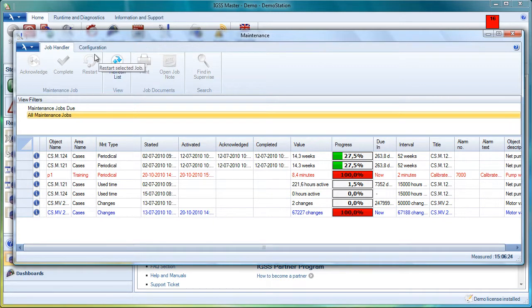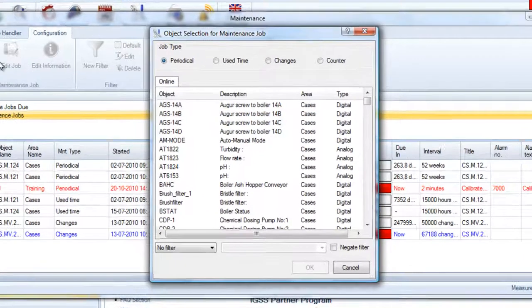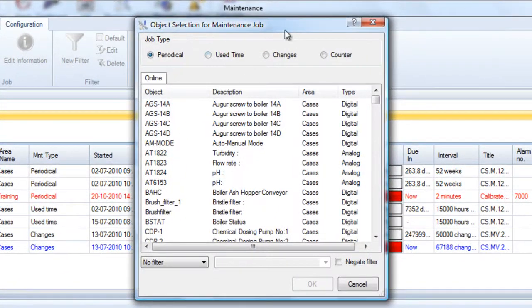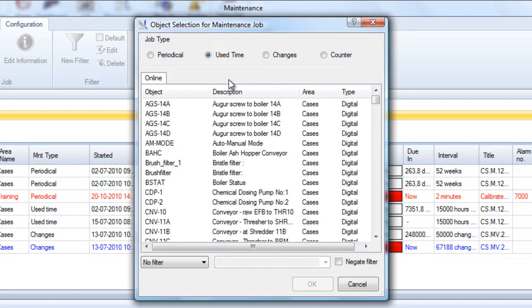Now let's create a job. On the configuration tab we click on the new job icon. We can choose, for example, a used time job, which means we are counting the hours of operation of a pump. Periodical job means you have a fixed maintenance interval. Changes maintenance means you are counting the number of state changes for a digital object.